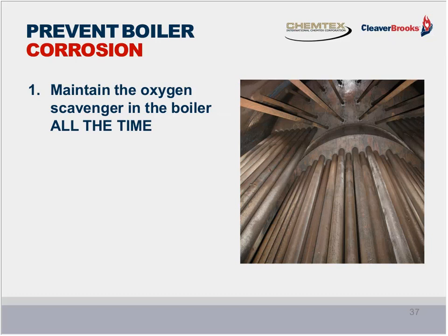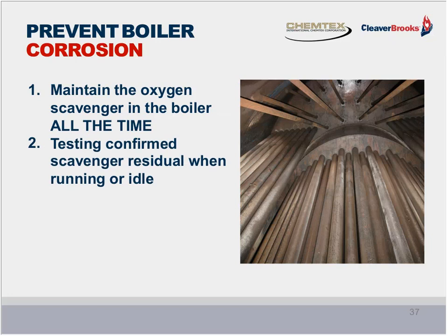And that includes testing the boiler for a confirmed oxygen scavenger residual when the boiler is idle and when the boiler is running. Idle boilers are frequently ignored, and the result is you've got 10 or 11 months of effective treatment taking place, in which case the other month that standby boiler is subject to severe oxygen pitting. And we're going to discuss a little bit more about that when we talk about wet storage of a boiler a little bit later in my presentation.